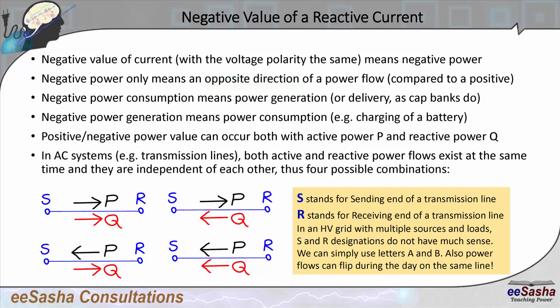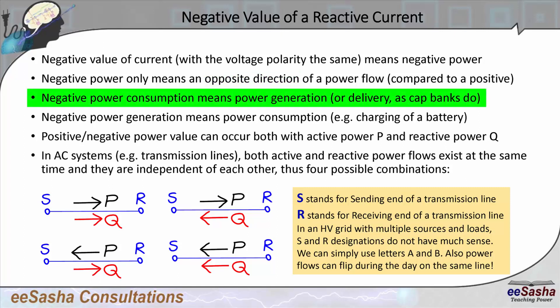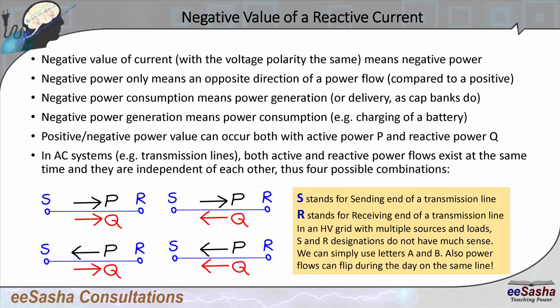Here are a couple of examples. If you have negative power consumption, that really means you have power generation. Normally for a cap bank, we say cap banks generate reactive power. However, it is the same as saying a cap bank consumes negative reactive power. Those two things are equivalent.